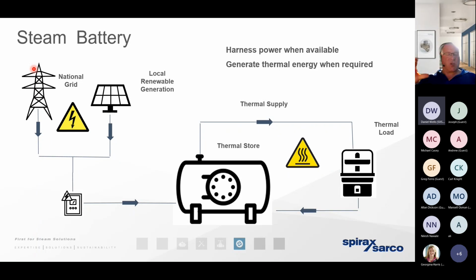So whenever we've got a requirement for thermal energy in the form of steam at the process, that can be realized by nothing more than depressurizing that vessel. That's when we get that flash steam effect that we spoke of. The water's going to boil off and change state to steam. In other words, we can distribute that steam to the process, to the heat exchanger, in exactly the same way that we were doing previously with the steam from the natural gas burner.